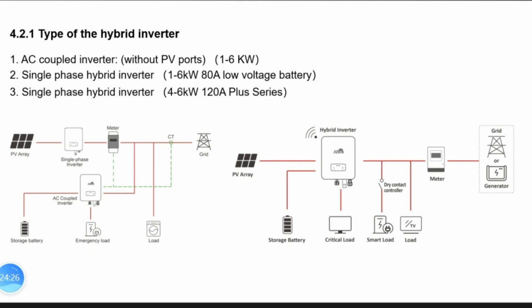And this part is for the new system. So you can connect the normal PV panels, storage, and power the critical loads. And you can also add the smart load. Smart load means some loads like a boiler. So when you choose self-use mode, when the PV panels cannot charge because the battery is fully charged and loads cannot consume the excess energy, the smart load will turn on to get this energy from the PV side. And the single-phase hybrid inverter also has the capability to connect with a generator as a backup or for peak shaving, with extra ATS kits.